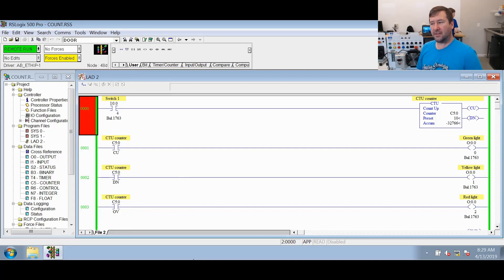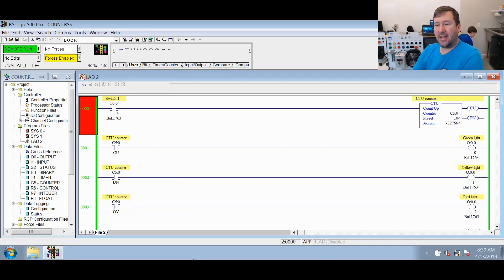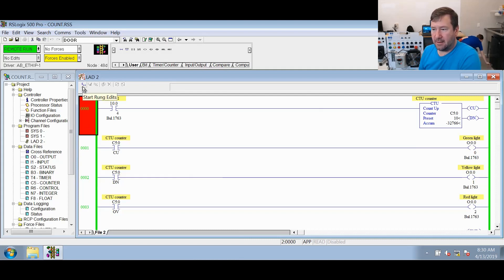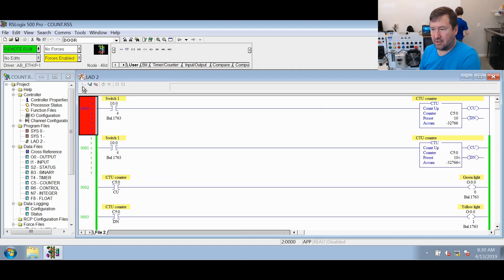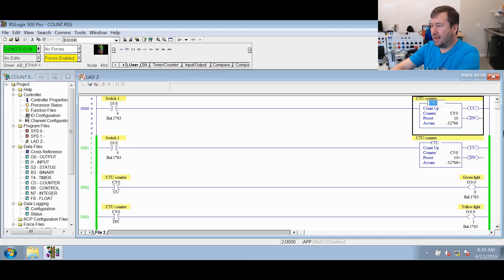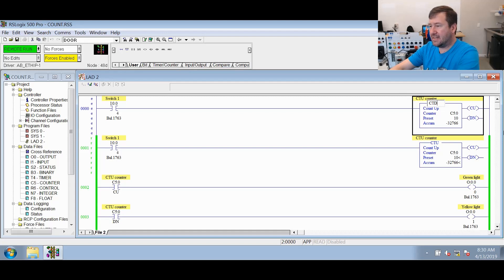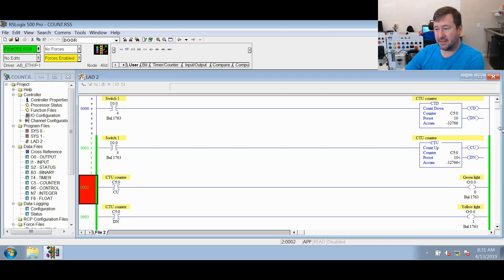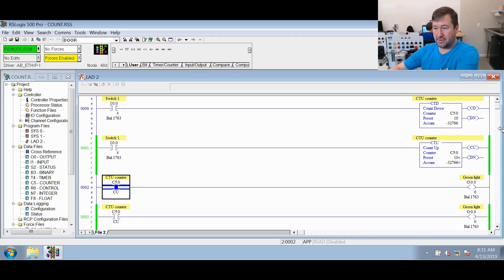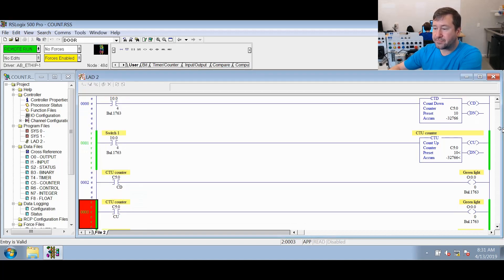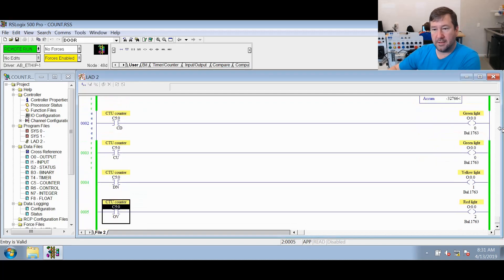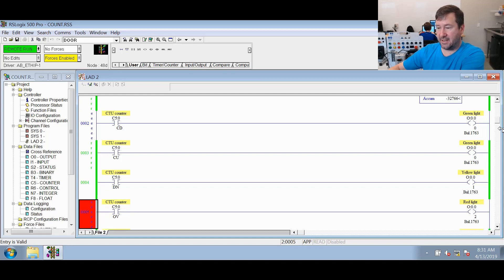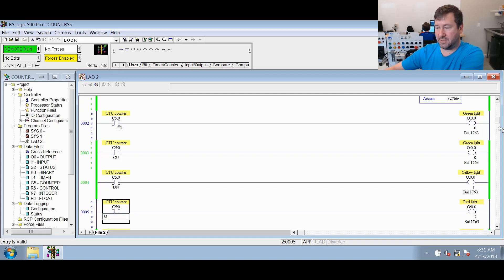All right, now let's go through the countdown counter. And to do that, we're going to make just a few changes to what we have. So we're going to use our online edits and we're going to select start rung edits. Then we're going to highlight the CTU and we're going to change it to a CTD. The CTD uses a little bit different format. Mainly the CU bit is not used. We're going to use the CD bit, which is a countdown enable. Then we're going to use the UN bit instead of the OV bit, which is the underflow bit.